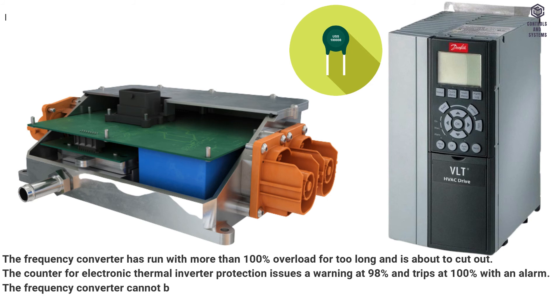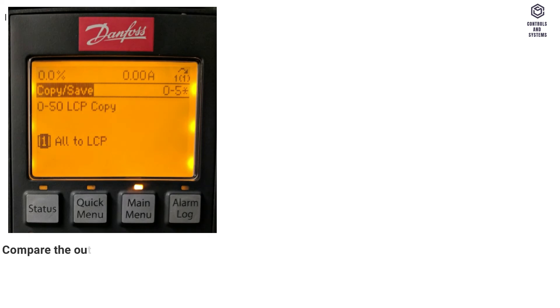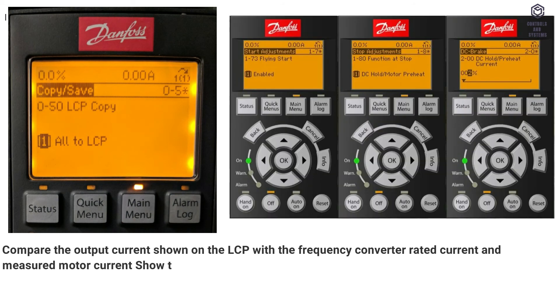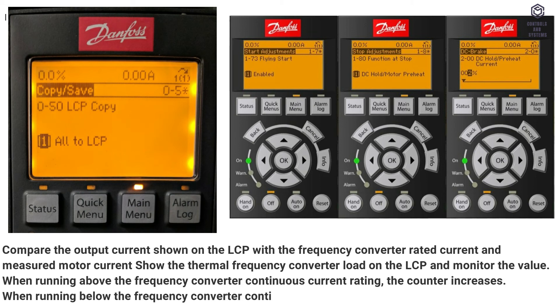The frequency converter cannot be reset until the counter is below 90%. Troubleshooting methods: Compare the output current shown on the LCP with the frequency converter rated current and measured motor current. Show the thermal frequency converter load on the LCP and monitor the value. When running above the frequency converter continuous current rating, the counter increases. When running below the frequency converter continuous current rating, the counter decreases.